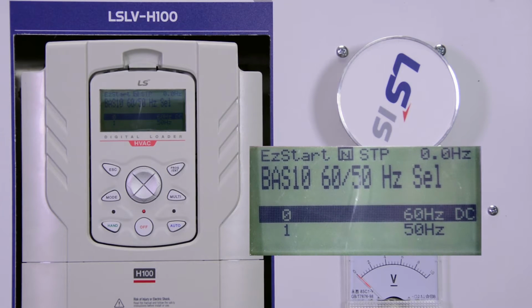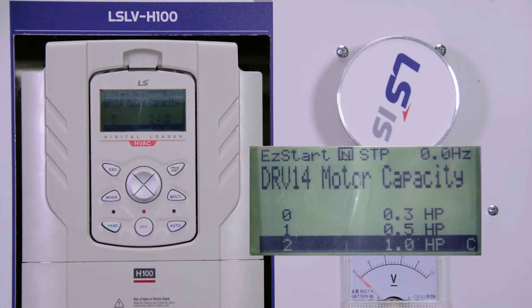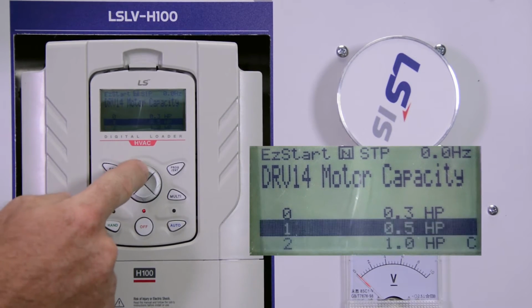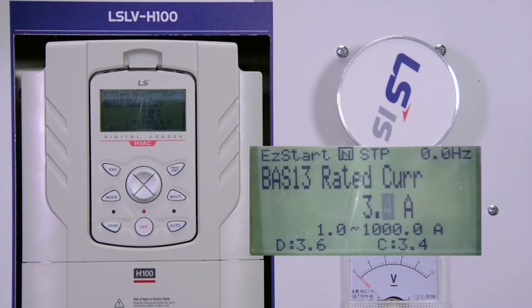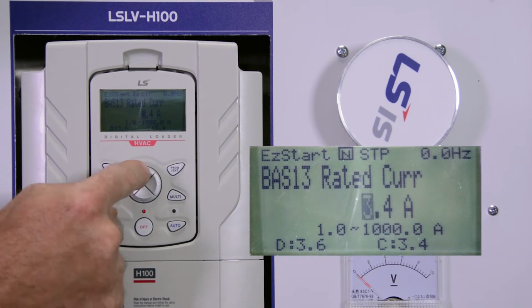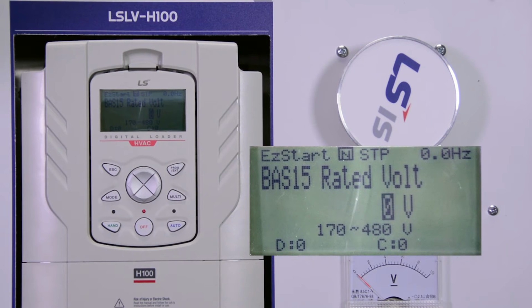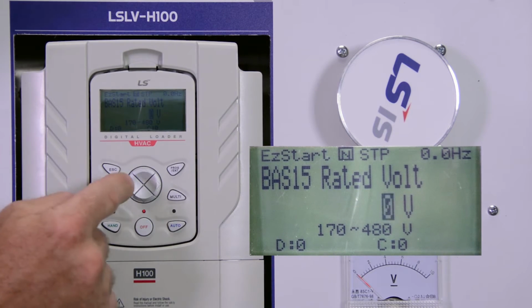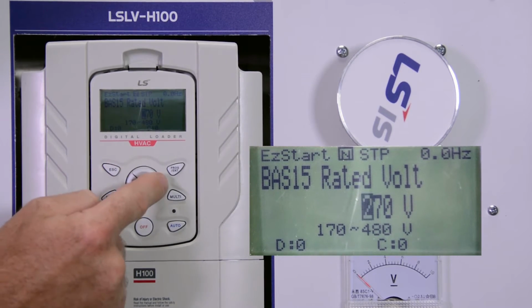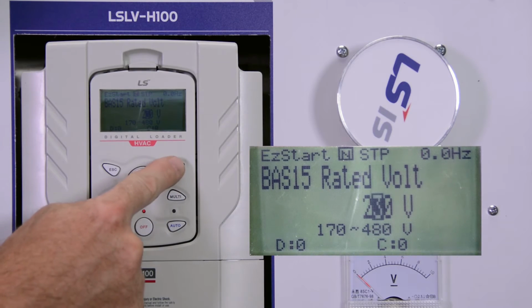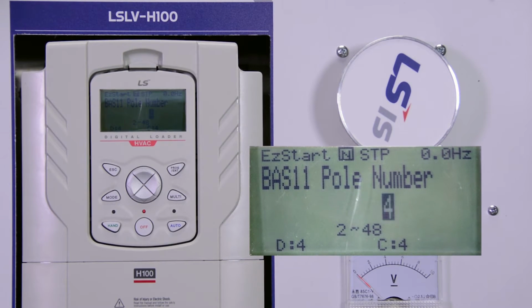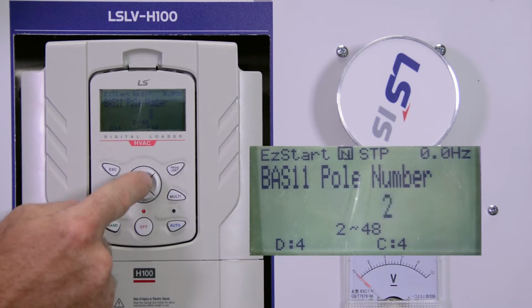Next question is, is the motor that you're using 50 or 60 hertz? And it is a 60 hertz motor in most cases. Then what's the motor capacity in horsepower? So we're going to select whatever horsepower it is. Next, we're going to select the motor rated current. Using your arrows, you can change it. Next question is, what's the motor rated voltage? We'll set it to 230. Enter. Then also the pole numbers. 4 is always our default value, but we can change it if necessary from there.